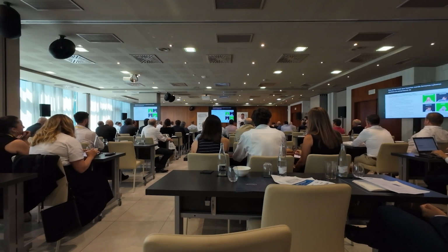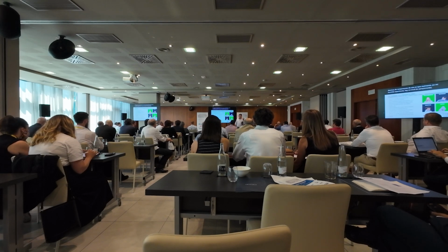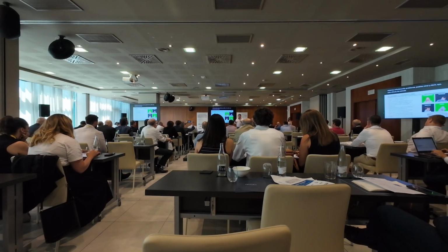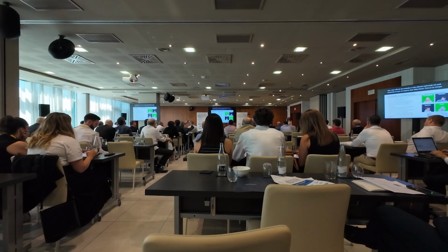One of the things when we're training young air compressor technicians is that there's really, in my humble experience, a component level, an equipment level, and then a system level. While we're troubleshooting, you might look and say, hey, this inlet valve or this solenoid valve isn't doing what it's supposed to be doing. But if it breaks once every 3 months for 2 years, do you think it's the valve?